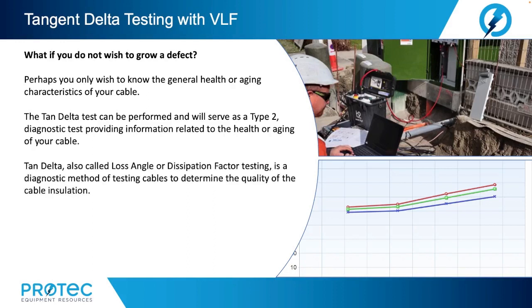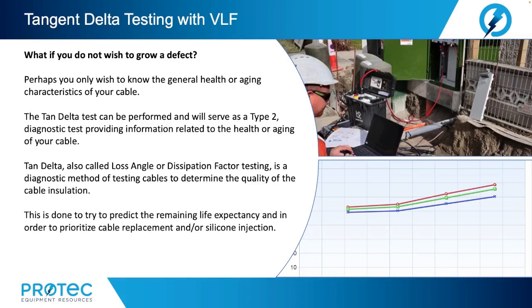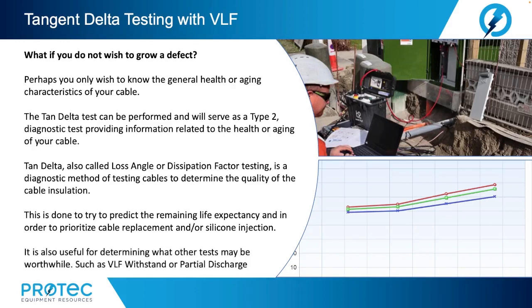Tan delta, also called loss angle or dissipation factor testing, is a diagnostic method of testing cables to determine the quality of the cable insulation. This is done to try to predict the remaining life expectancy and in order to prioritize cable replacement and or silicone injection efforts. It is also useful for determining what other tests may be worthwhile, such as the VLF withstand or partial discharge testing.